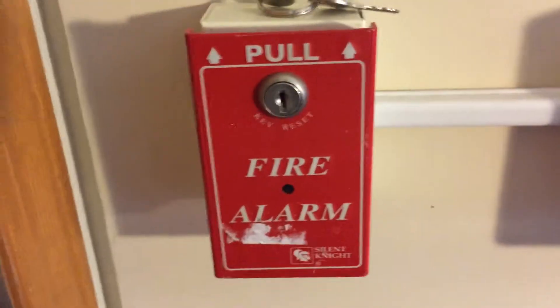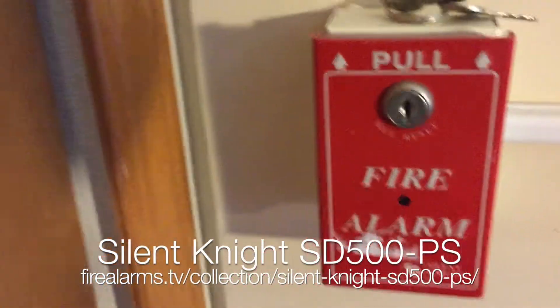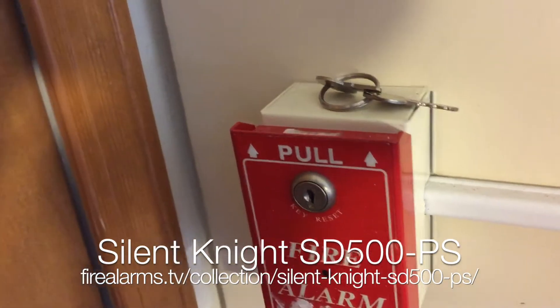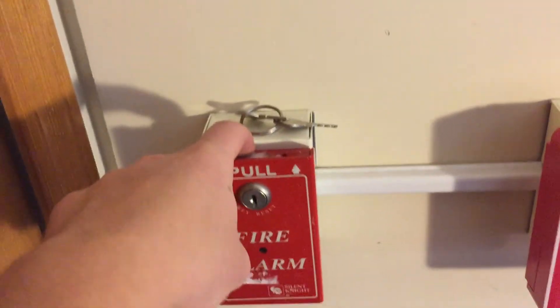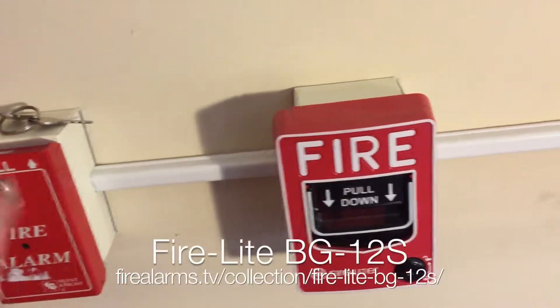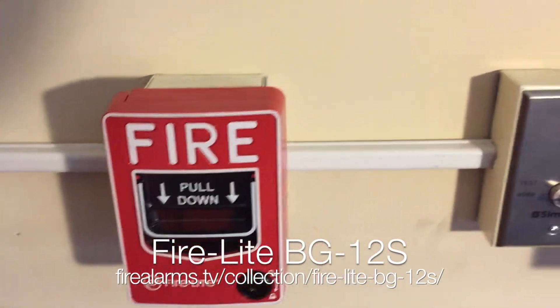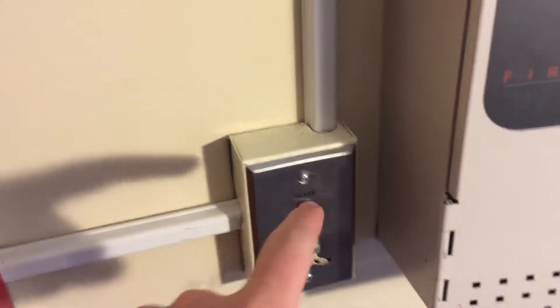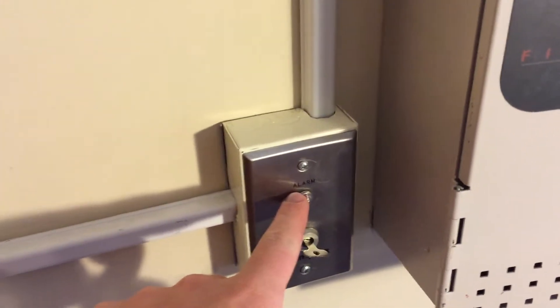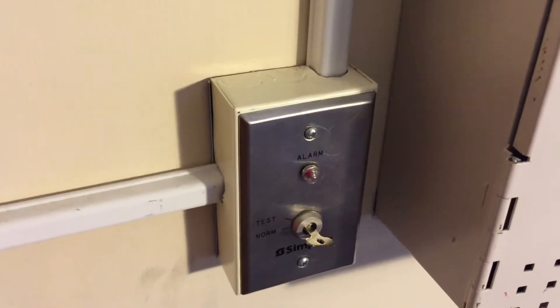Moving over to the devices: the first one is this Silent Knight pull station — I forget the model number, but it pulls like a BG-8. That'll be the first thing I set off; this is Zone 1. Next thing I have is a BG-12S, fairly standard, fairly simple. This is actually on Zone 3, because the indicator on the test switch — the auxiliary power, for some weird reason — wasn't working on any zone but Zone 1 or 2, so I just went ahead and switched these two.